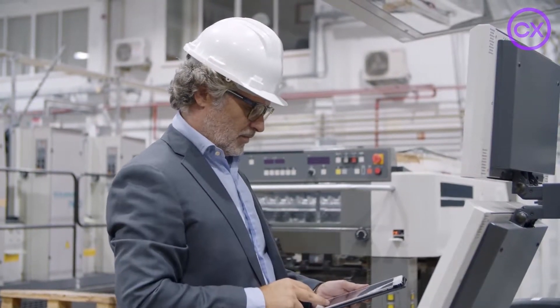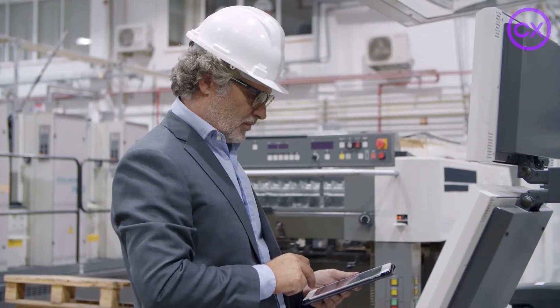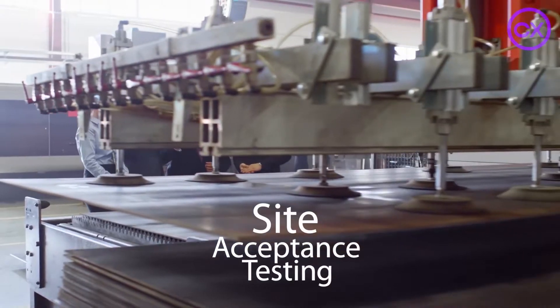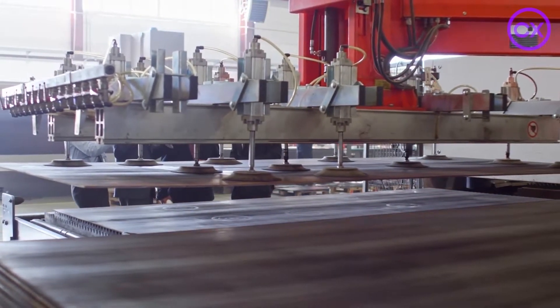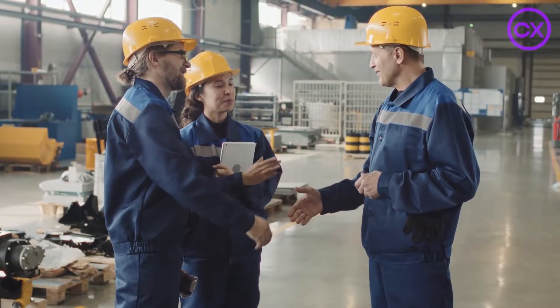There are a few terms related to off-site and on-site testing. FAT, or factory acceptance testing, is the testing conducted by the manufacturer in the factory prior to shipping to site. SAT, or site acceptance testing, is the testing conducted in the field either by the vendor or by the on-site commissioning team — these are standalone tests to confirm no damage during shipping or installation. SIT, or site integration testing, is the testing conducted in the field to confirm equipment functions as a system.